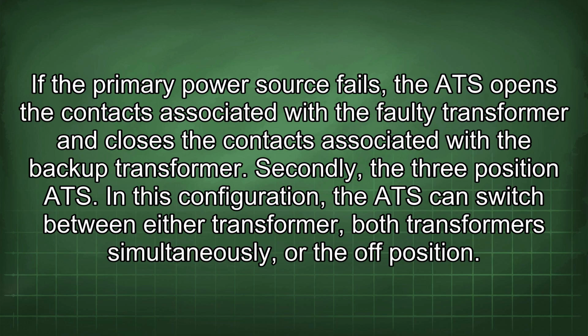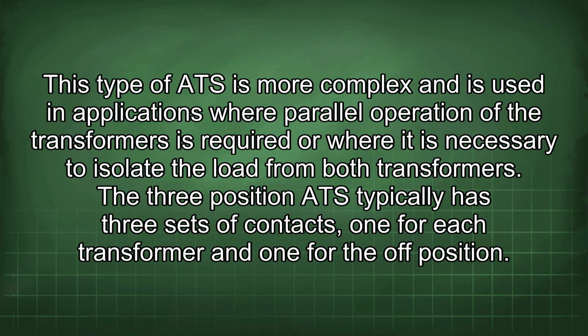Secondly, the three-position ATS. In this configuration, the ATS can switch between either transformer, both transformers simultaneously, or the off position. This type of ATS is more complex and is used in applications where parallel operation of the transformers is required or where it is necessary to isolate the load from both transformers. The three-position ATS typically has three sets of contacts, one for each transformer and one for the off position.